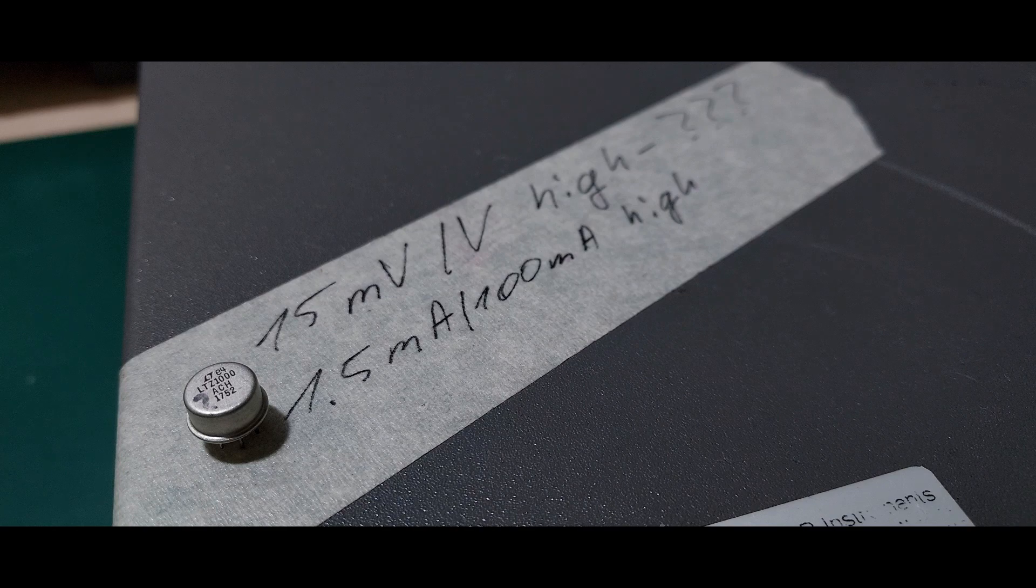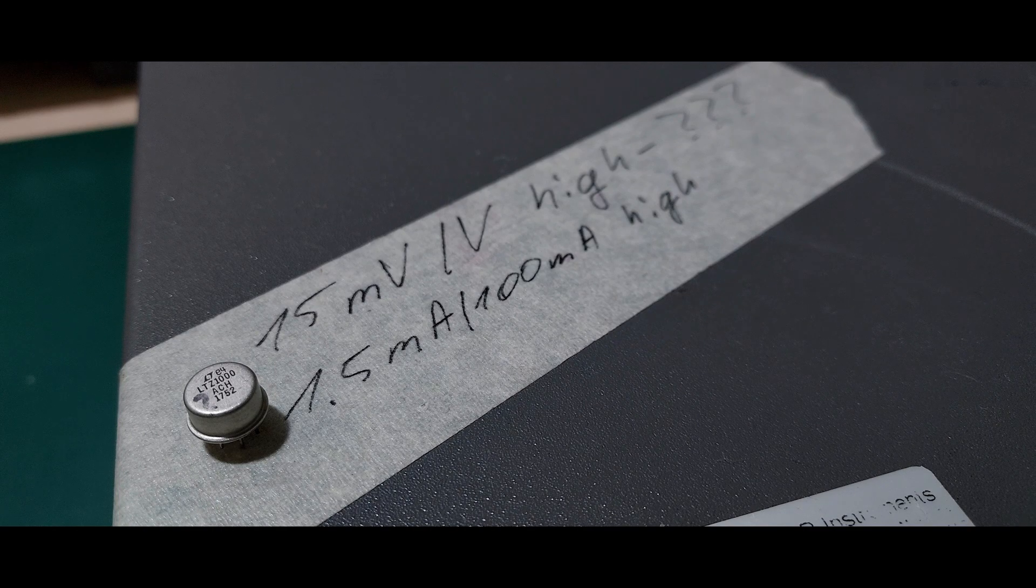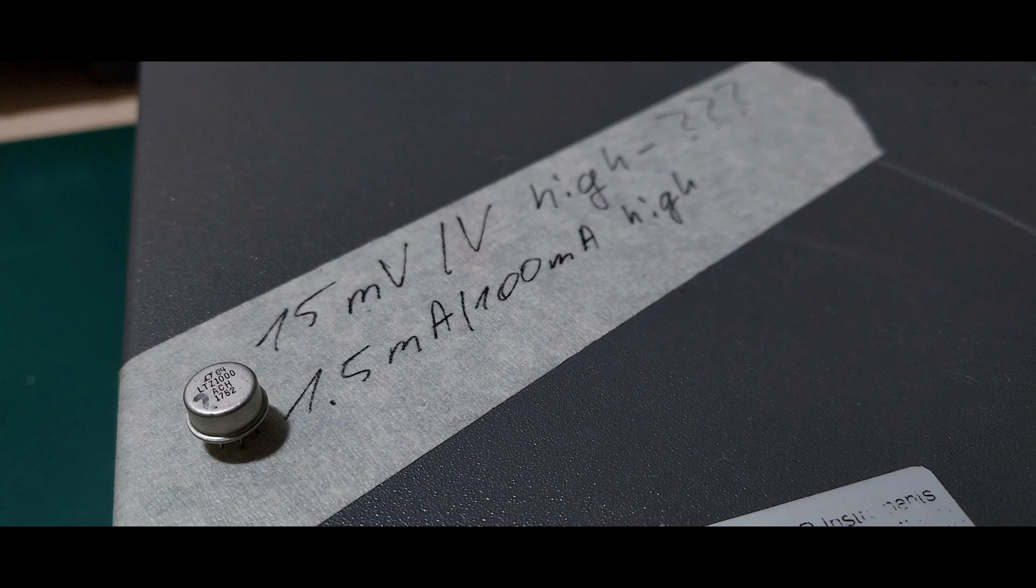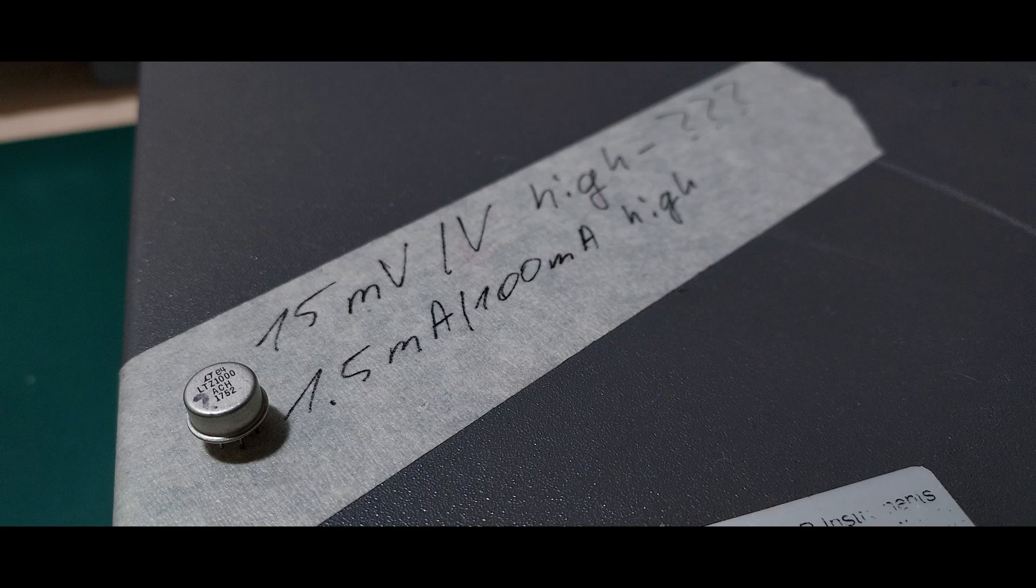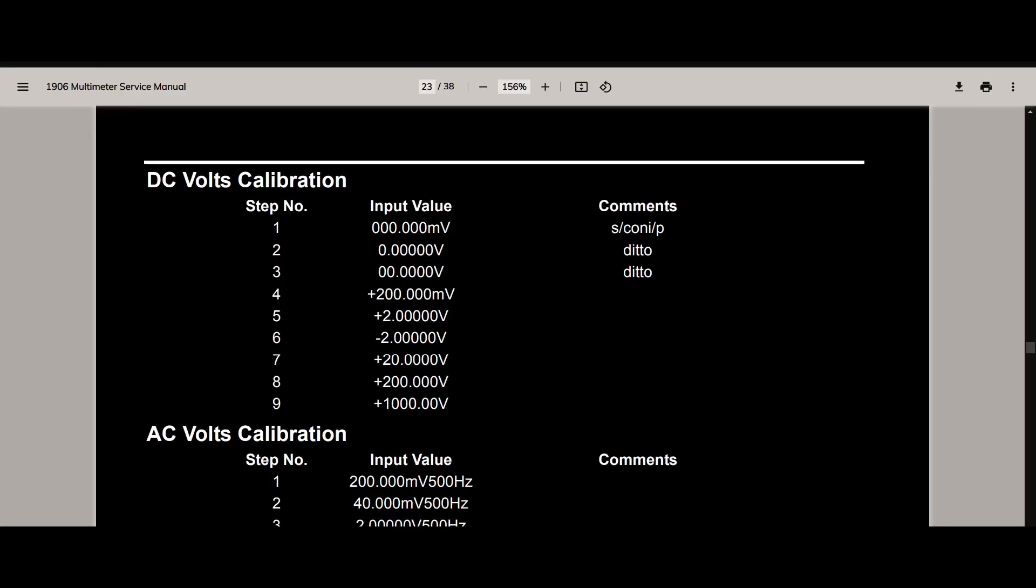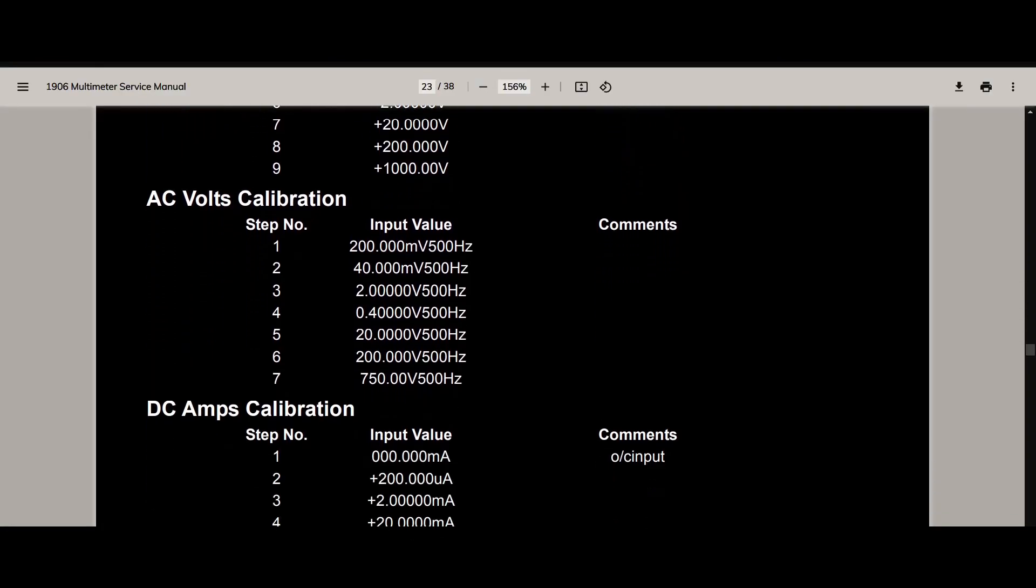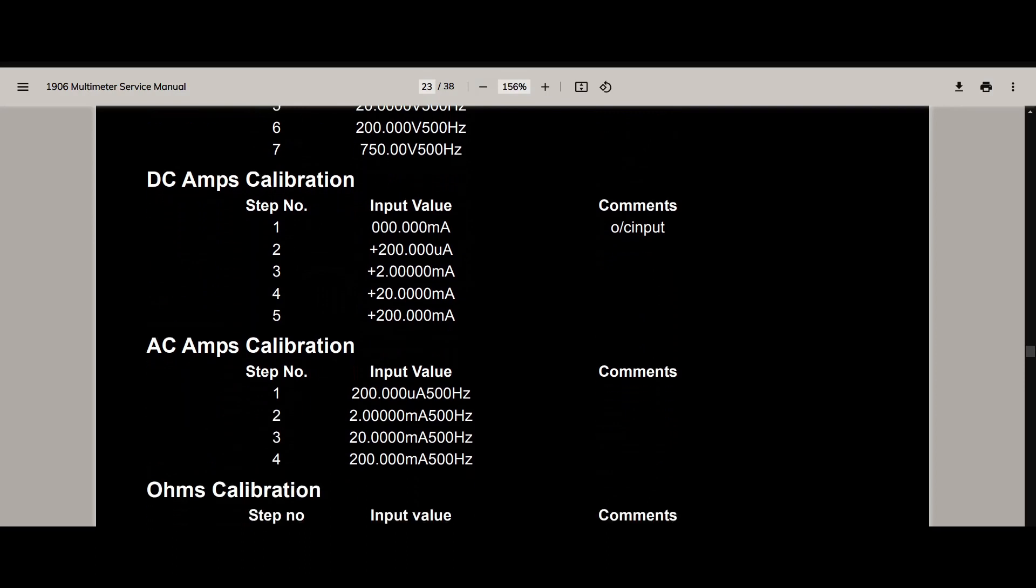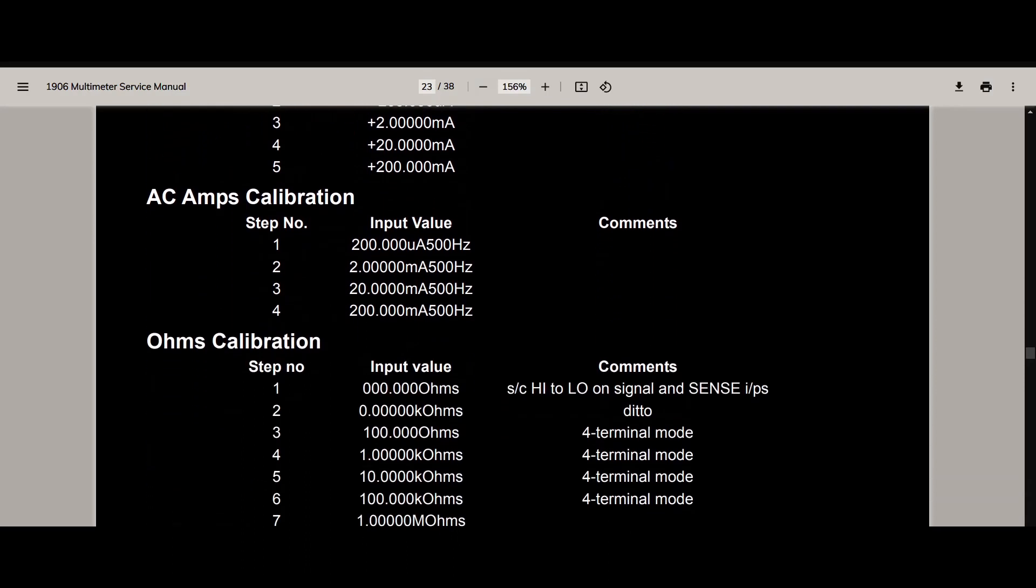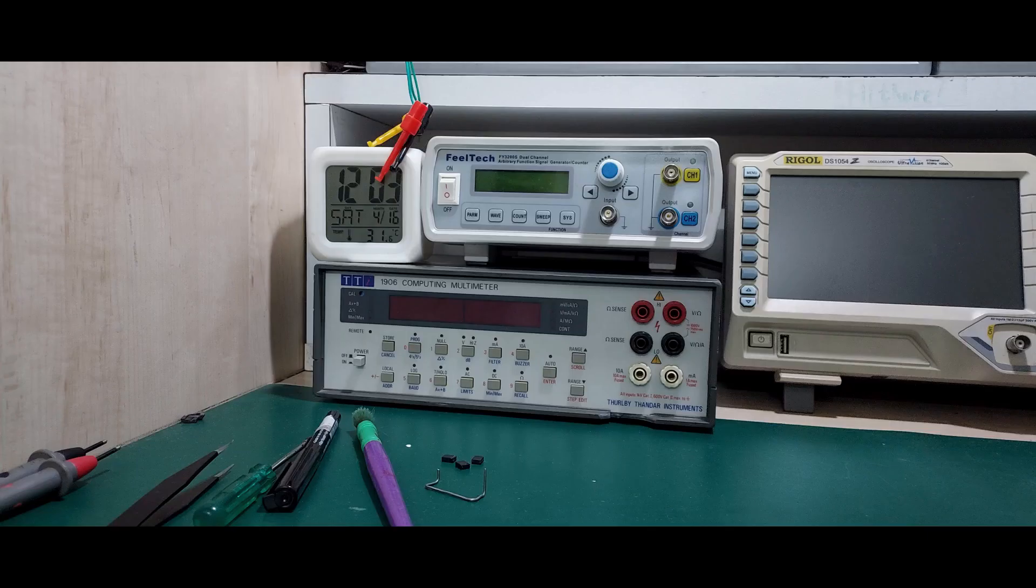One quirk with the TTI 1906 is that every range for each function must be calibrated. I cannot calibrate, say, the 20V range alone. This is slightly inconvenient since I need an accurate 200 millivolts to 1kV DC source which I don't have and couldn't find.